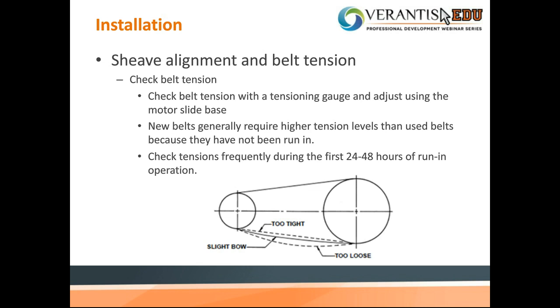During your belt tension, if you don't check it, they are set at the factory, but as Craig said, over time they will loosen because of the run-in time. If you don't retension those belts, you'll see a black dust in the belt guard or under the canopy. Eventually those belts are going to continue to wear down and potentially even cause wear on the sheave, and you would have to end up replacing not only the belts, but the sheaves too, if it's let go long enough.